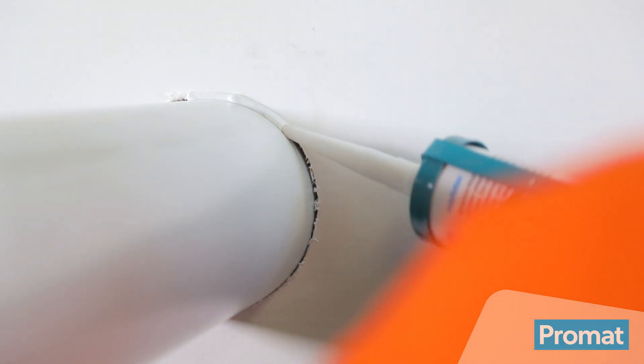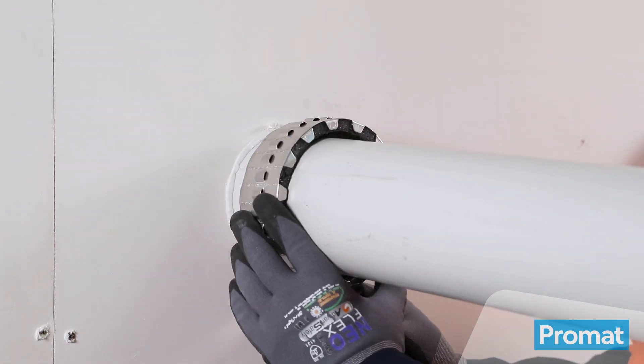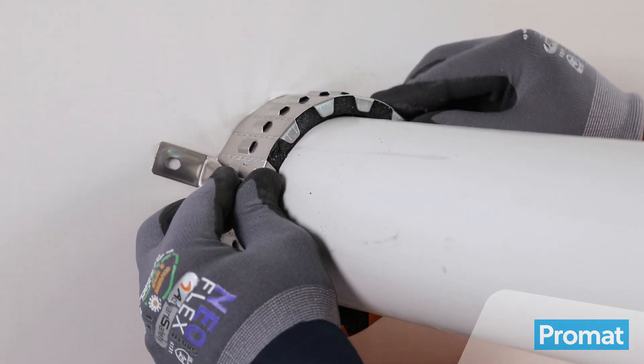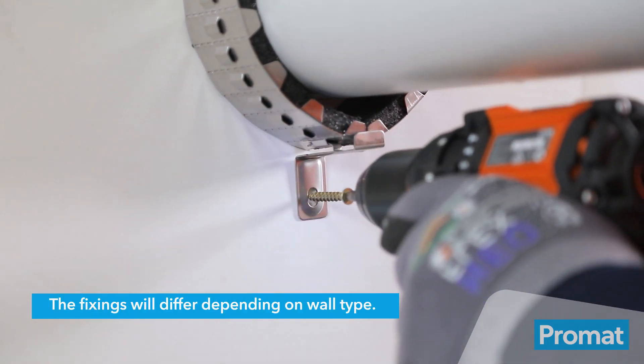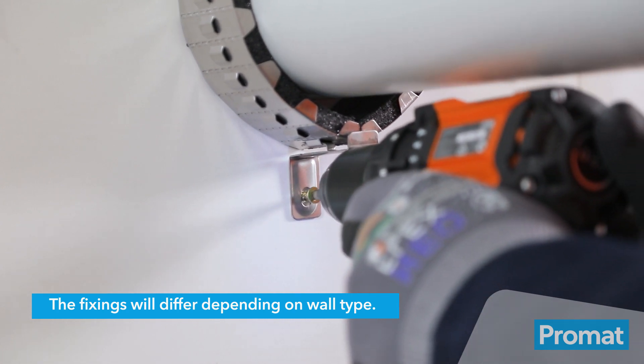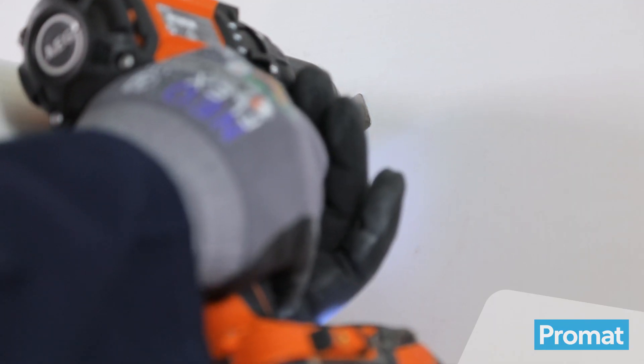Seal the gap between the pipe and the wall with Promaseal A acrylic sealant. Place the Promastop UniCollar around the pipe and evenly place the remaining brackets on the strip. To attach the UniCollar to the wall, use the metal screws and fasten to the wall through the holes in the UniCollar brackets. To complete the installation, repeat the process on the other side of the wall.